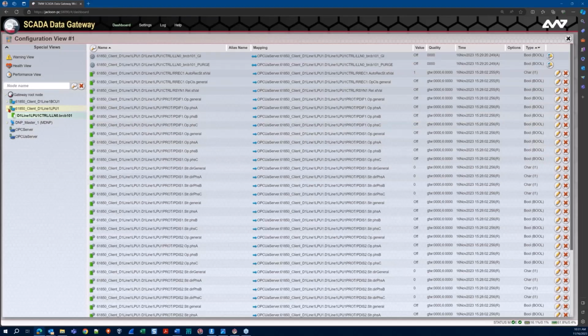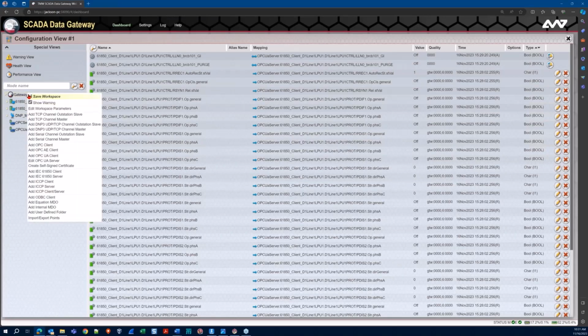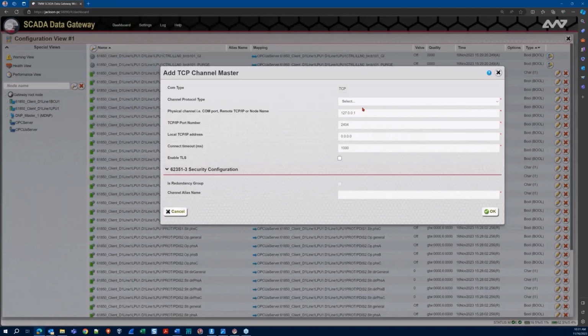To do that, much like I did before with my 61850 client, I'm going to right-click on the gateway root node. We group a couple different protocols together within this 'add TCP channel master' option. I'll click that, and that's how I'm going to create my DNP3 master. I need to specify that it is a DNP3 master from that dropdown. Like I said, we've lumped together 101, 103, 104, Modbus, and DNP.